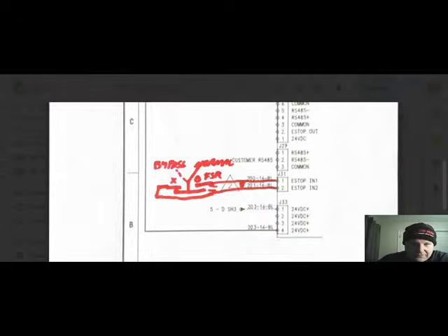So you can see this is poorly drawn, but this is normally open. When the switch is in the normal position, this is going to be open. We are maintaining the loop with this right here. We switch this to bypass. This is going to close and maintain the loop. And then it doesn't matter what happens with this fire suppression relay. It's not going to make any difference because the loop's being maintained through this manual switch.